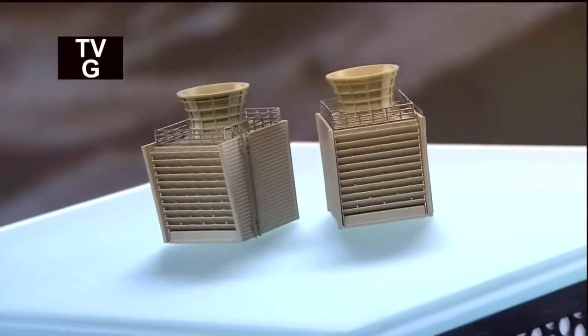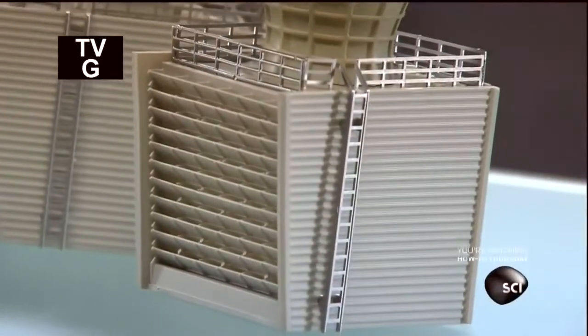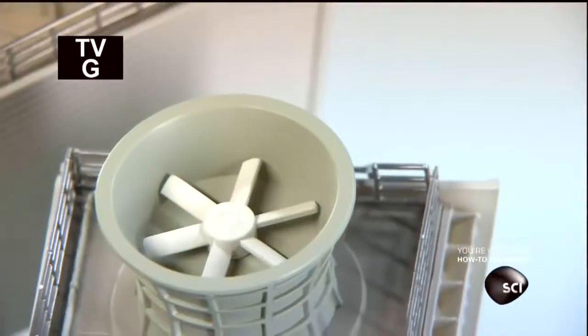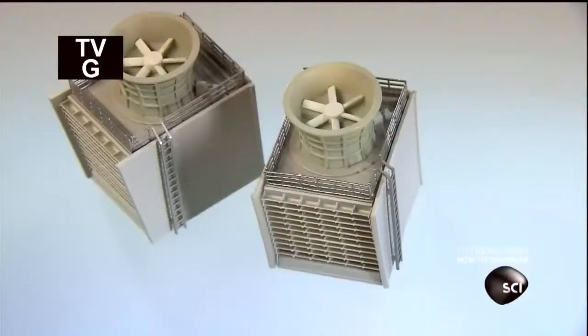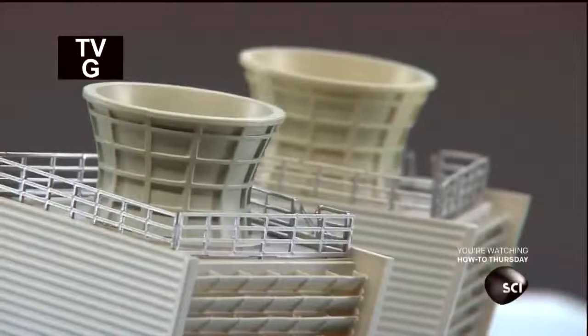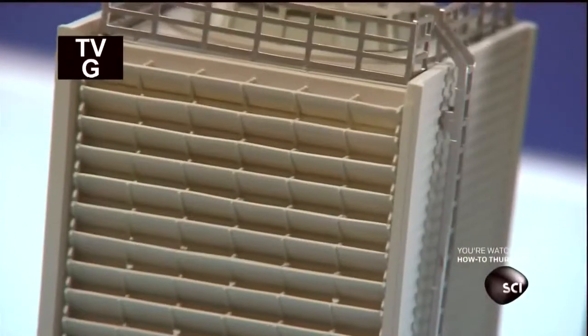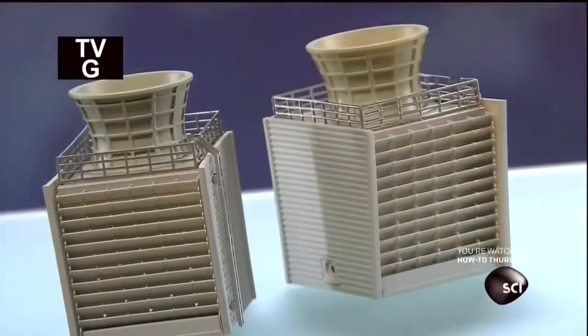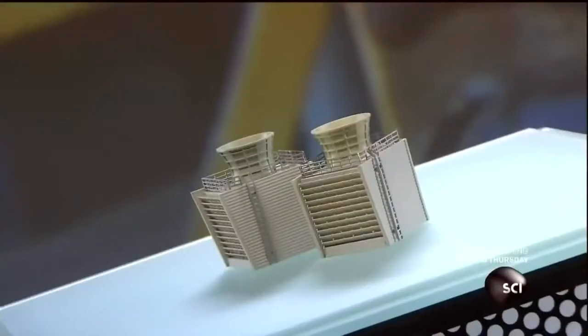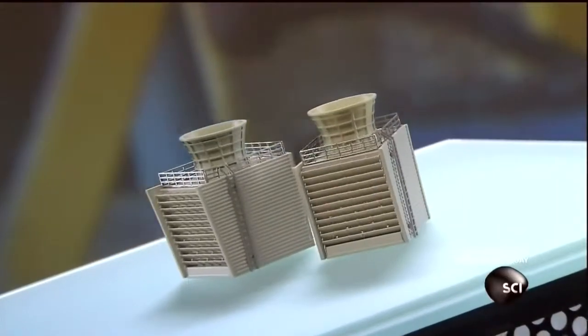Evaporative cooling towers keep large buildings and industrial machines cool. Circulating liquid carries the excess heat to the cooling tower, typically installed on the roof. The tower uses cold water to cool that fluid, then transfers the heat to the atmosphere through an evaporation process.